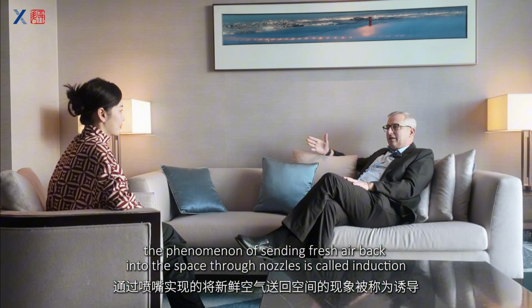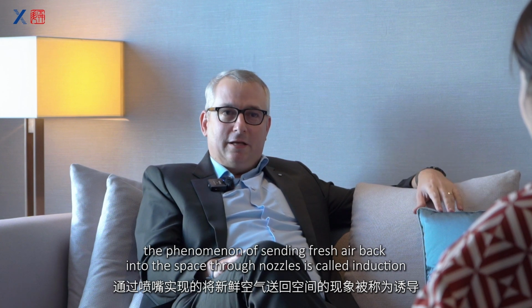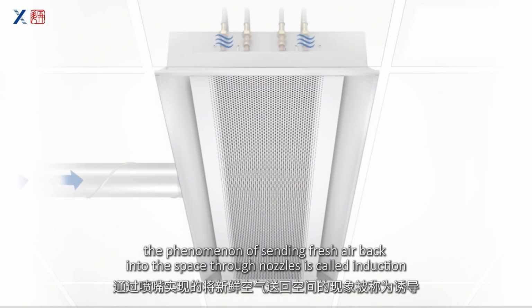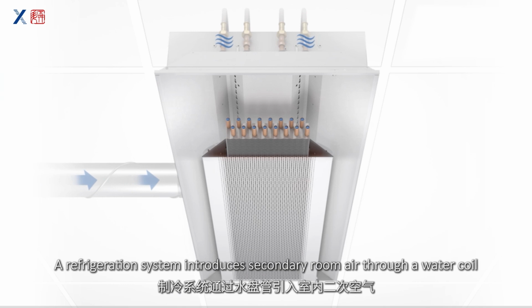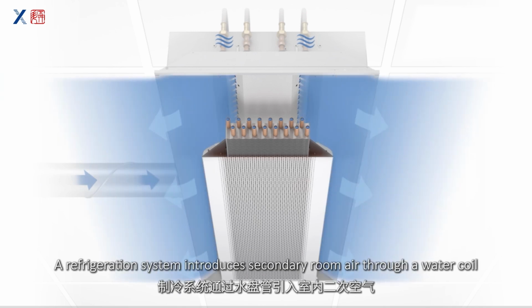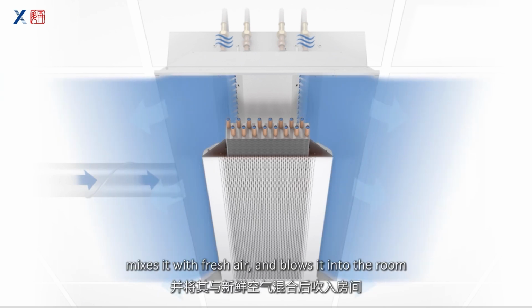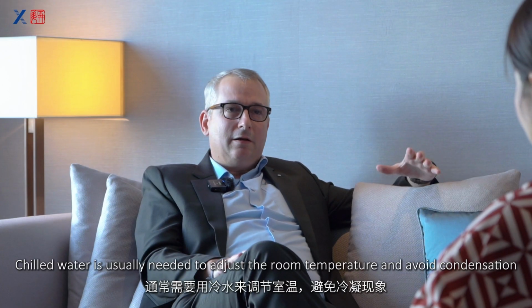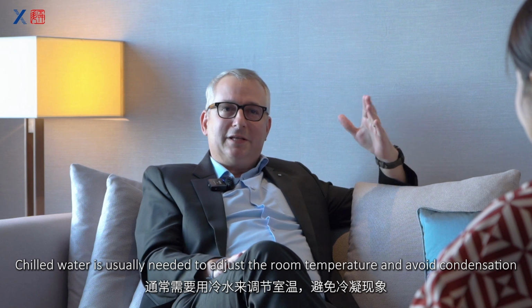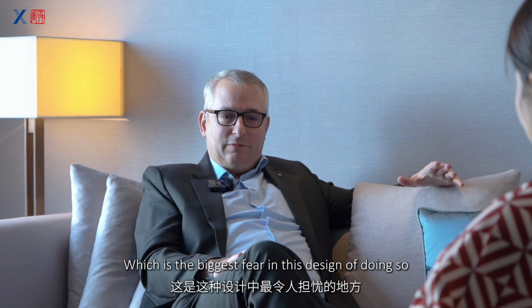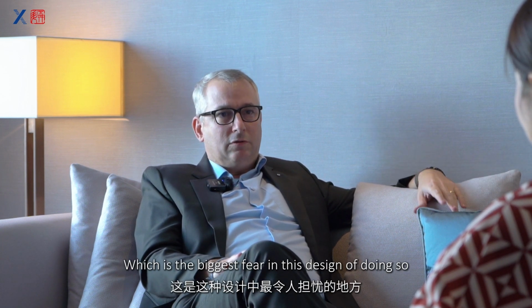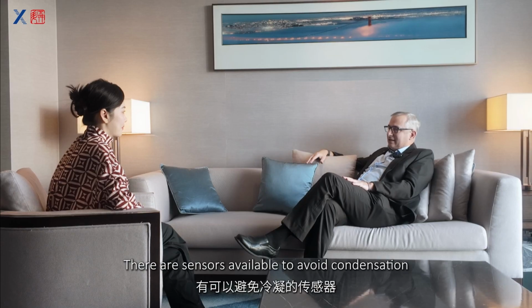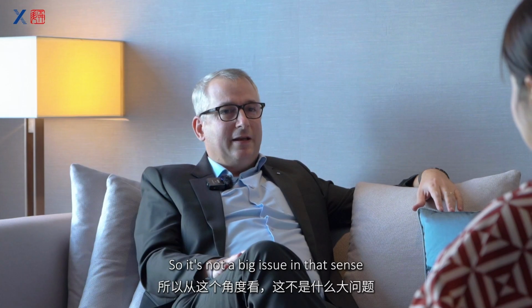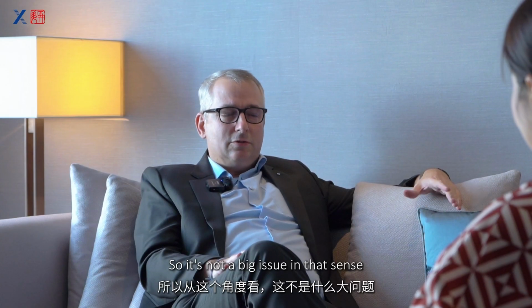It's called induction, which happens with the nozzles. With induction we're introducing secondary room air through a water coil and mixing that with the fresh air, blowing it into the room. The chilled water is typically 1 degree above room dew point to avoid condensation, which is the biggest fear in this design. But there are sensors available to avoid condensation, so it's not a big issue anymore.